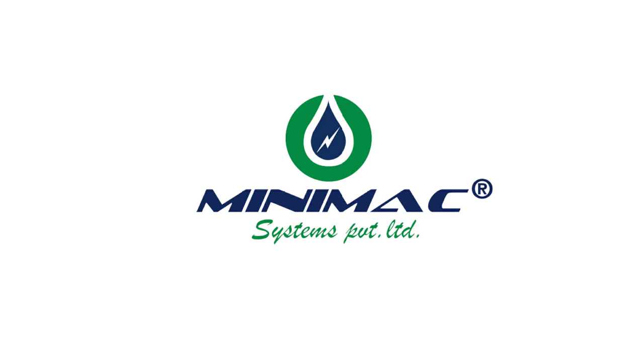In RILA, we do checking of highlights of the report, like what the practices are, what the trends were in the last few months or year, and what we can optimize. Can we optimize the frequency of lubrication, whether it can increase or decrease? Then contamination control strategies like sealing of the system, putting positive pressure inside the work hall or equipment room. There are many things. Oil analysis program: what should be the frequency of oil testing? That should be optimized, because if you test the oil of the whole booster oil pump every 15 days, that is waste of money and time. Every 1 month, again, it is waste of time.